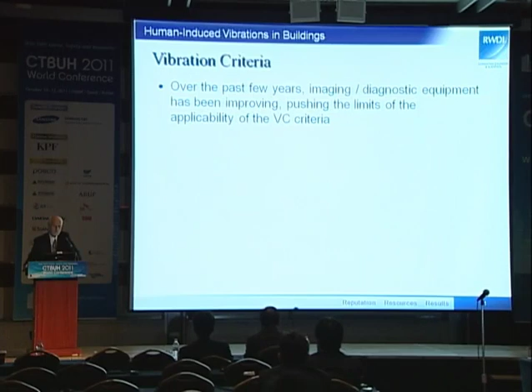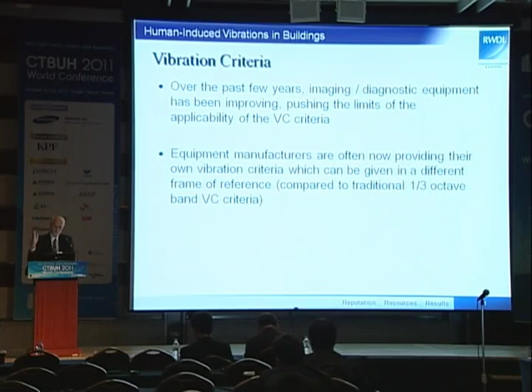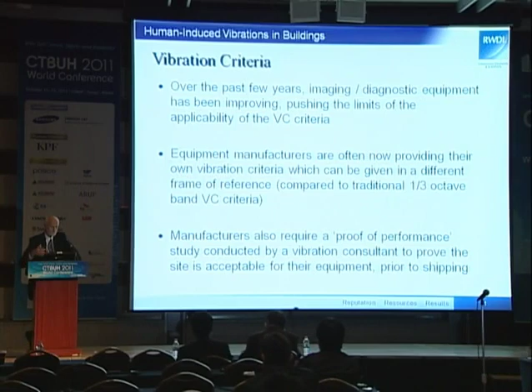Over the past few years, imaging and diagnostic equipment has been improving, but as the equipment improves, it makes the requirements for vibration criteria even more stringent. Equipment manufacturers are now often providing their own vibration criteria, not in the traditional 1/3 octave bandwidth, but over much narrower frequency ranges. If they know their equipment is going into a given space, they will require proof of performance that the space is suitable. The study has to be undertaken by a vibration consultant to prove that this site is acceptable before they'll ship the equipment.